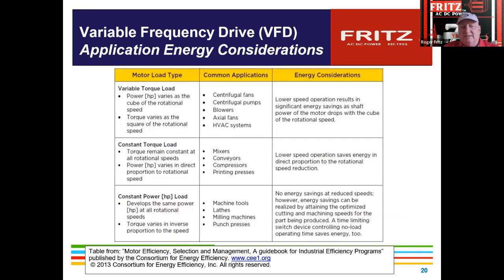Let's see. So this is a sheet that talks about variable torque loads, constant torque loads, and then constant horsepower loads, which are areas where you really don't have too much opportunity. What they mean by that is a machine tool, a lathe, milling, punch presses and those things. On a punch press, you may want to slow the cycles down, but you really can't do much speed control in here. So it's got to stay at constant horsepower. You don't see a lot of savings.